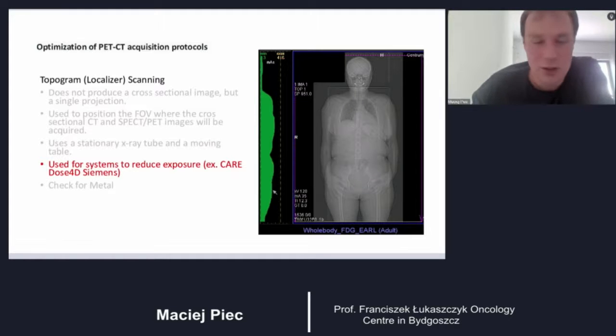And rather quickly, a few tricks that you can use to reduce the dose administered to the patient. I haven't divided it between PET and CT because these examinations are quite close to each other. When we are using PET-CT technology, we start with a topogram. This is important because I'm not sure whether it works for all manufacturers, but I know that for most of them, the topogram image is important for systems that reduce the dose or the exposure for the further part of the examination.